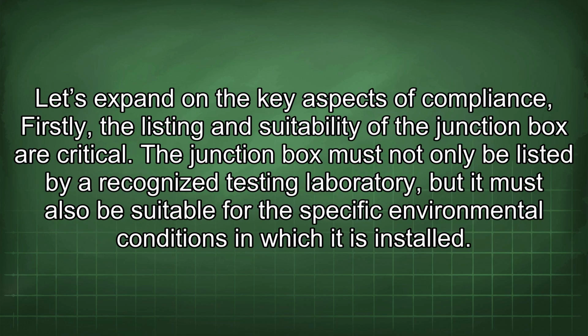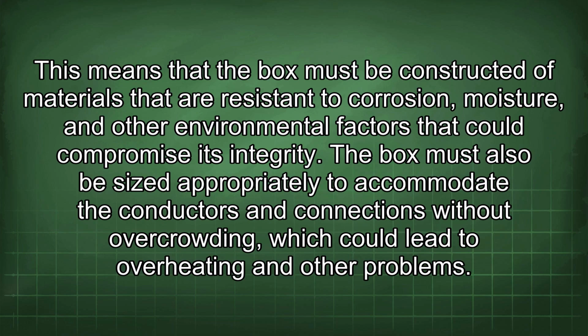Let's expand on the key aspects of compliance. Firstly, the listing and suitability of the junction box are critical. The junction box must not only be listed by a recognized testing laboratory, but it must also be suitable for the specific environmental conditions in which it is installed. This means that the box must be constructed of materials that are resistant to corrosion, moisture, and other environmental factors that could compromise its integrity.